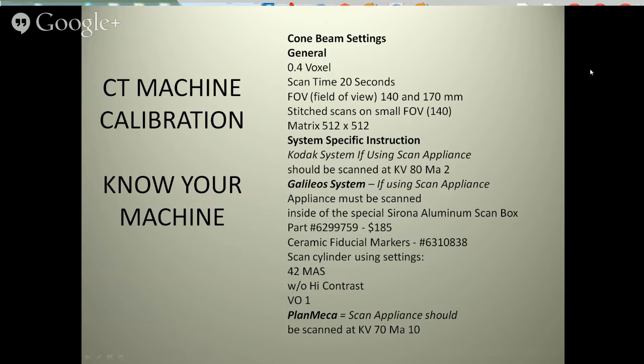There are a couple of machines to mention. The Kodak system should be scanned at a KV of 80 and an MA of 2, which is different from other machines, so you really have to pay attention to the calibrations on the machine you own.